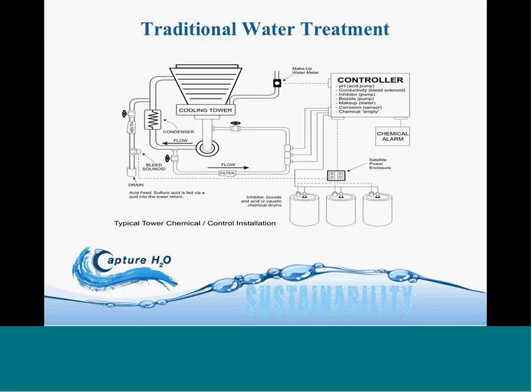Traditional water treatment, if you look at a building cooling system, you have your cooling towers, which are designed to evaporate water to reject the heat that you're removing from your HVAC equipment, like a chiller or a plate and frame heat exchanger. Water is recirculated through that system, and the minerals that are in that system are constantly concentrating up because you're evaporating off pure water. So these systems need to make up with fresh water constantly, and then also you'll have a controller that's attached that's sampling that water and determining the dissolved solids levels, and then you have a solenoid valve that needs to dump when the levels get too high.